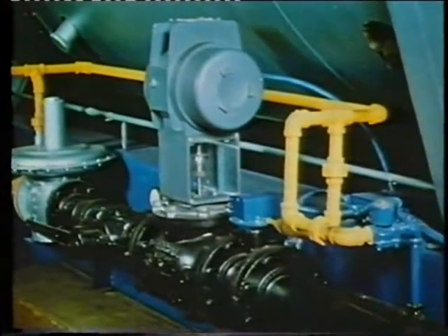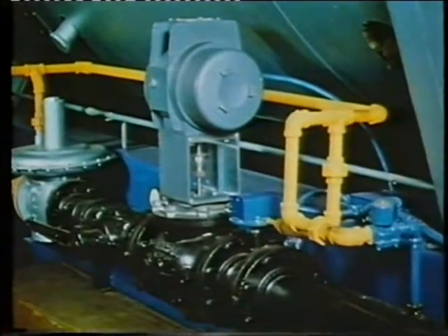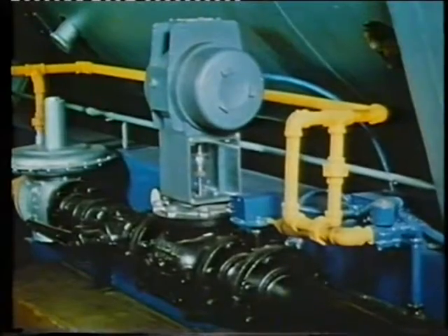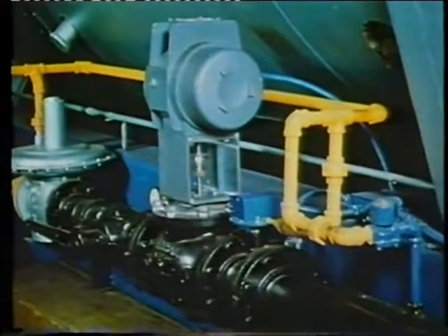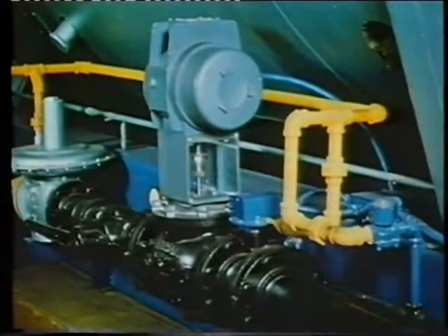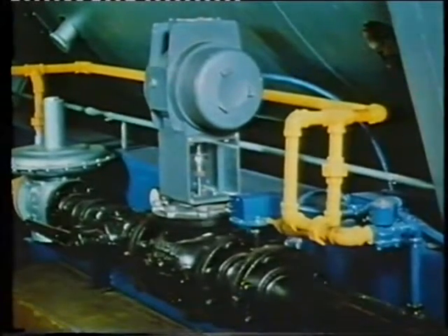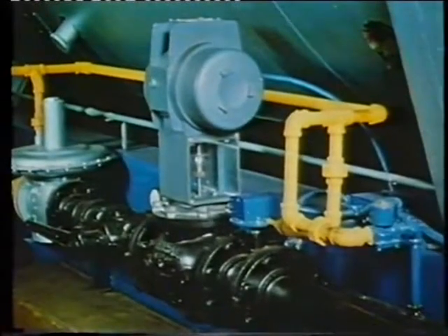The motorized main gas valve is an electrically activated shutoff valve. In the event of any boiler malfunction, such as flame failure, low water, or excessive steam pressure, this valve springs closed to shut down the main burner. Insufficient gas pressure, detected by the vaporstat, would also cause shutdown. During the normal ignition and combustion cycle, this valve is opened and closed by the programmer.